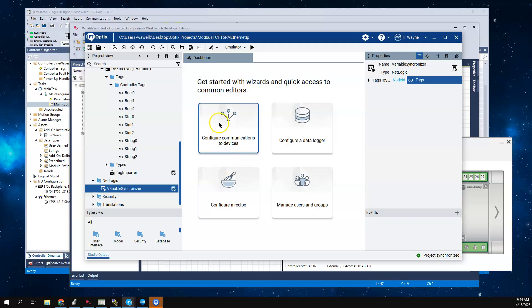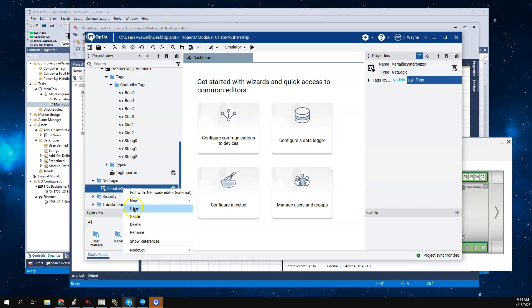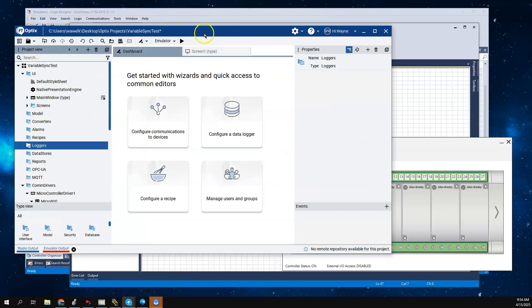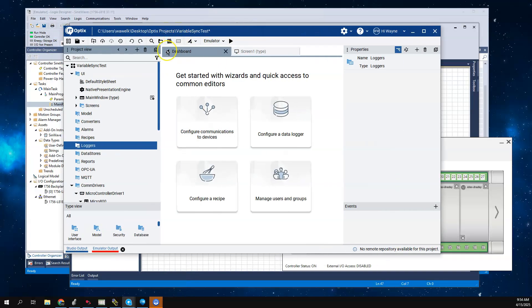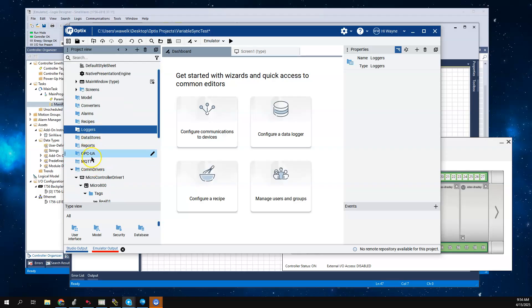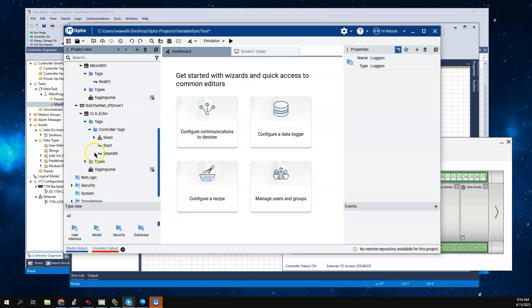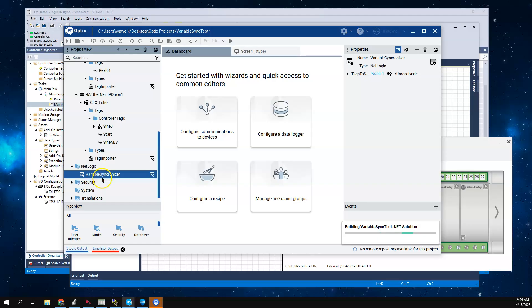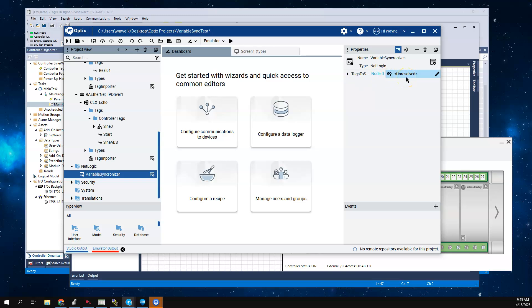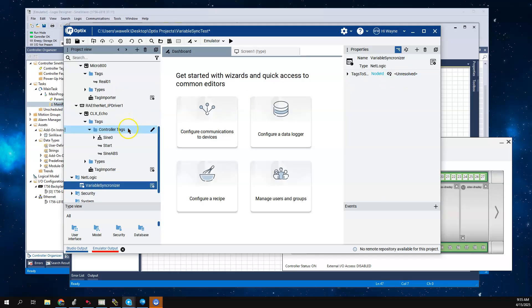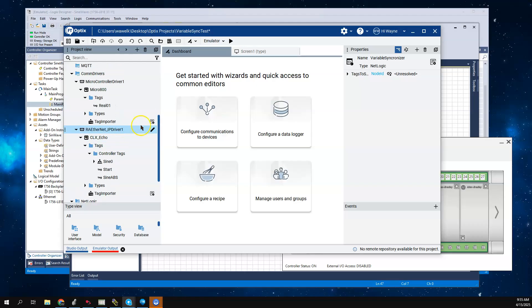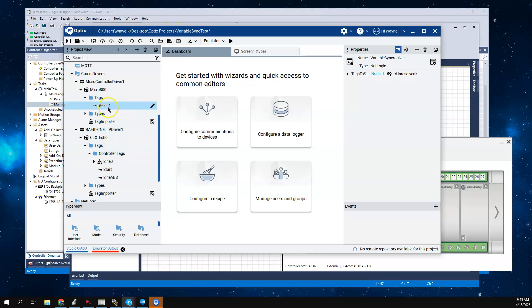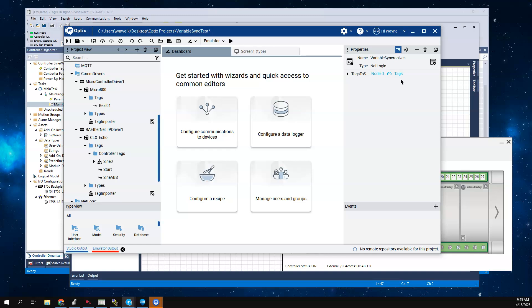What's kind of nice about this is I can take this C# script right out of this sample program. I'm just going to say copy. Now I'm going to go back to my other Optix application. I'm going to come to my NetLogic folder, right click, and say paste. Now my Variable Synchronizer is here. Note that the tags to sync is unresolved. To resolve that, I'm going to point this to the tag folder of the tags that I want to sync, which is the Micro 800. I can take this tag folder and drag it to right there. That's actually all I have to do.